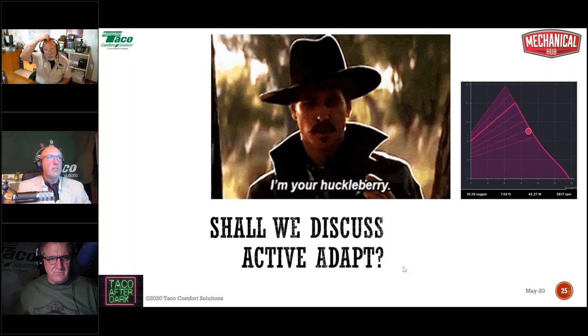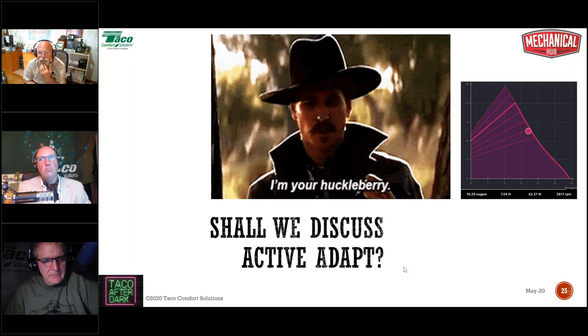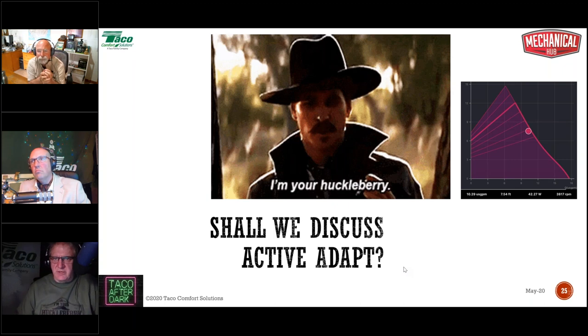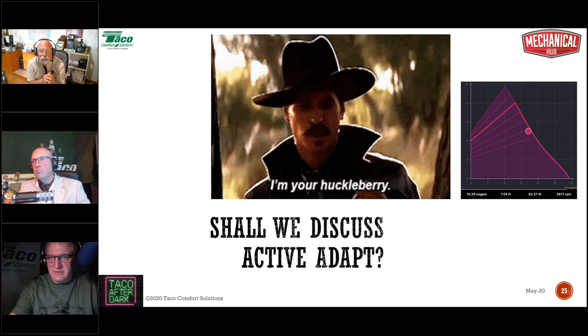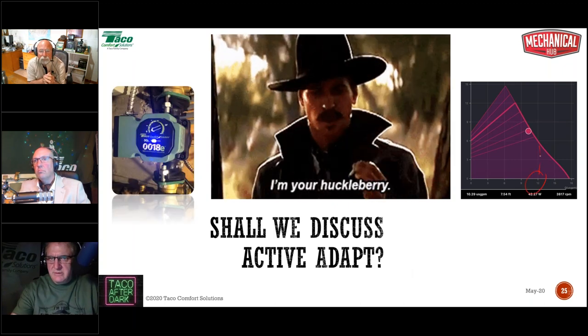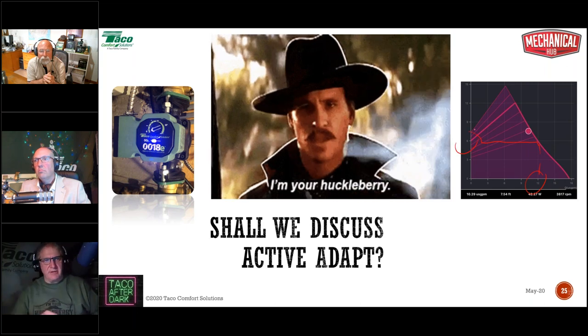Mike Lampkin, I think you've got a bigger blow up of the actual curve, but his question is, Mike, if you look real close, you can see at 12 gallons a minute, you follow that up to maximum speed, you're right at about 6 feet of head. So hopefully that answers your question. Okay. Yeah, he's looking right about here, right? 12 gallons a minute. Yeah. 6 feet of head. There we go.